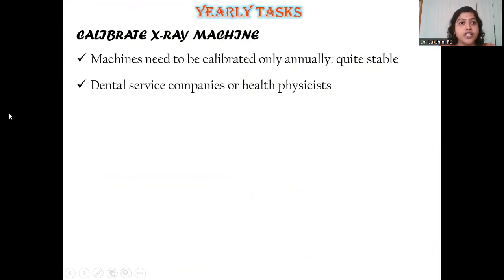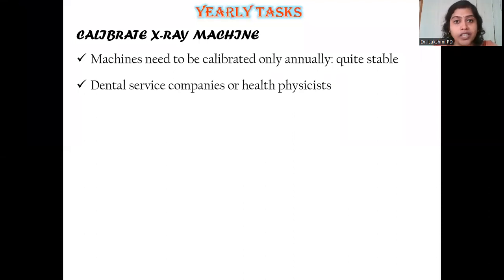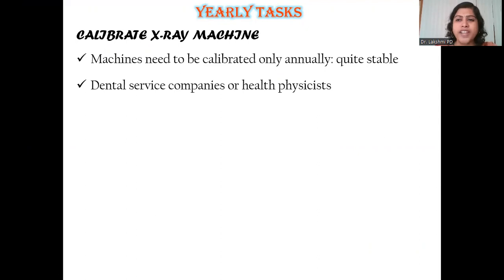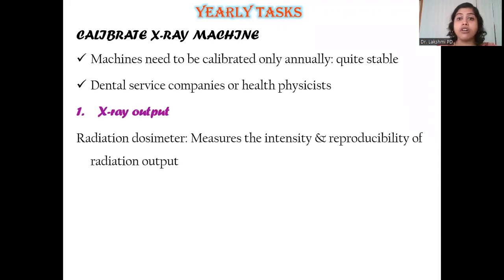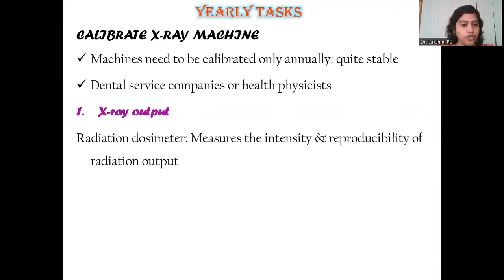Moving on to the yearly task — done at the end of every single year — which is calibrating your x-ray machine. You do not do this daily, weekly, or monthly. X-ray machines are quite stable, but at the end of the year, dental servicing should be done by dental servicing companies or health physicists who will perform acceptance tests — a set of tests to ensure all parameters are adequate and at proper functioning levels. The first check is x-ray output, done using a radiation dosimeter to measure the intensity and reproducibility of the radiation output.